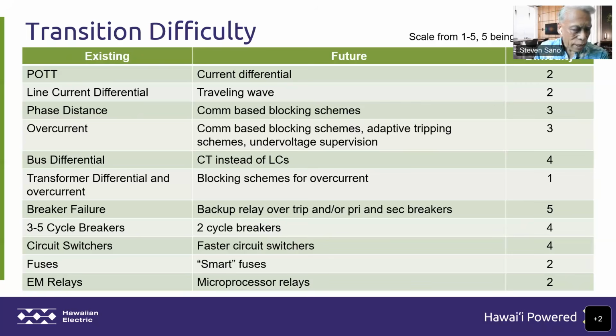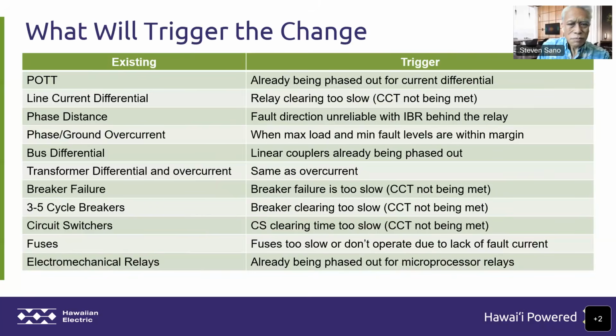of thing. Electromechanical relay replacements with microprocessor relays. We've been doing that. We just need to keep on doing that to get the electromechanical relays off and keep the current microprocessor relays up to date. So difficulty, we gave it a 2. And again, this is really just our subjective rating of the difficulty. It could be different at different companies and different locations. Okay, this next slide takes a look at what we think will trigger the change for these protection schemes.